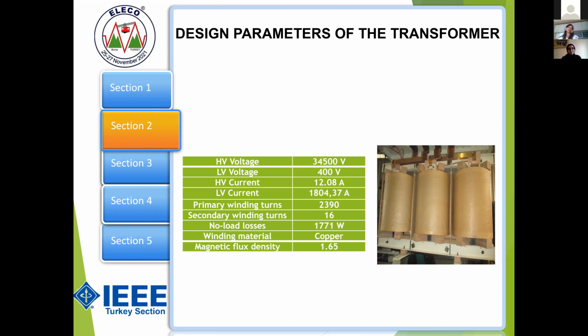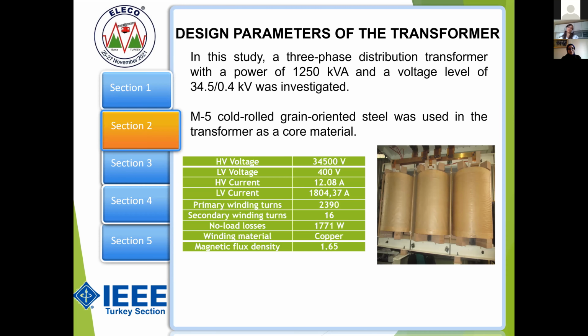So these are some of the parameters of the transformer. In this study, we have used a 3-phase distribution transformer rated 1.25 megavolt-ampere, with a voltage level of 34.5 kV, meaning 34,500 volts, and 400 volts, which was investigated. In the core, we have used M5 CRGO steel material.